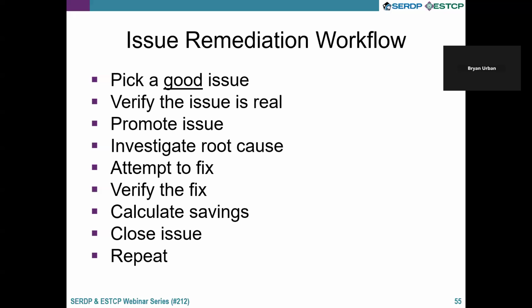There are ways to filter on issues that are happening now or only recently, so if you send a tech into the field, they'll be able to see the issue is actually happening and help troubleshoot it—you don't want to waste people's time. Then you promote the issue in the system, assign it a tracking number, investigate the root cause, add notes, attempt to fix, and verify that it's fixed. Symmetrics would then calculate energy savings using energy models that combine weather data and real operational data to estimate savings for the major faults identified. Then you close the issue and repeat the process.